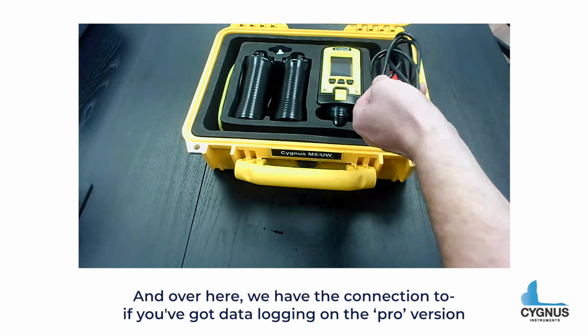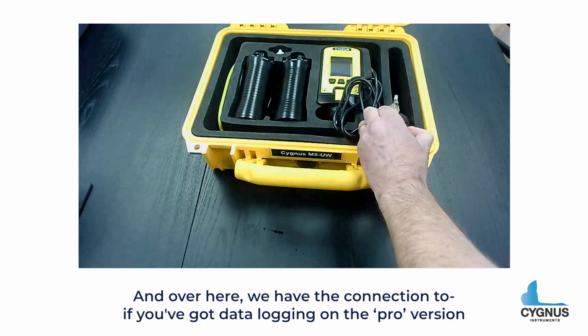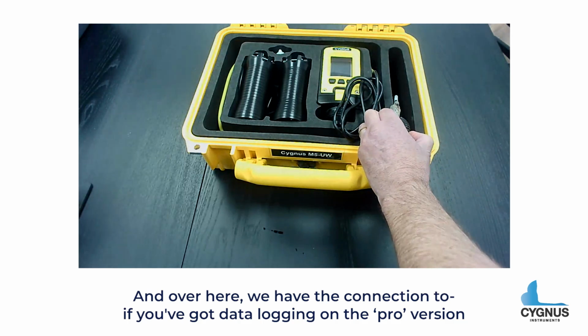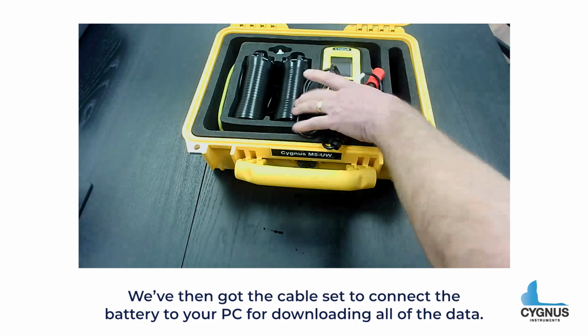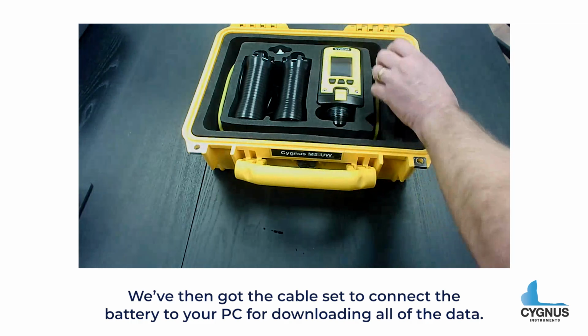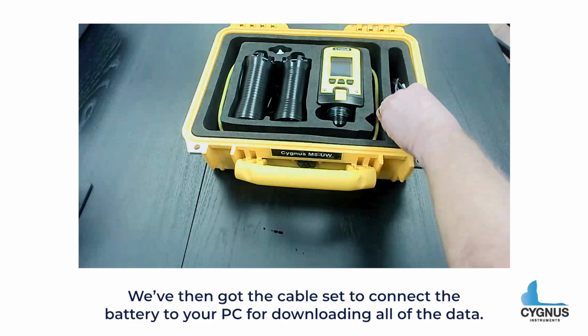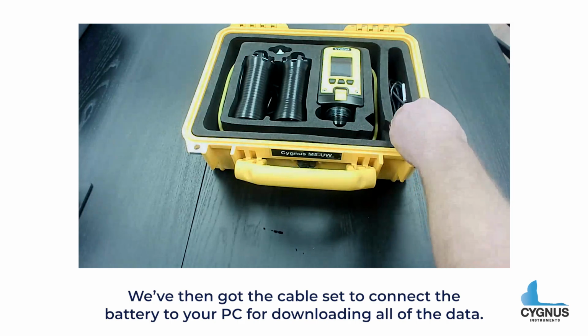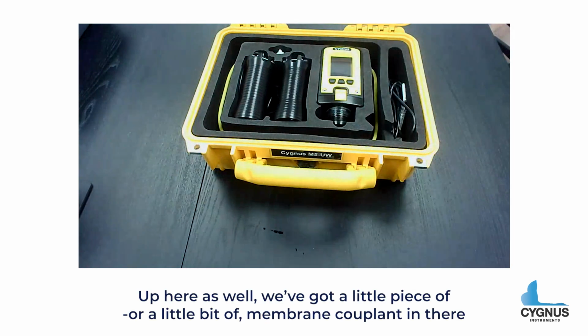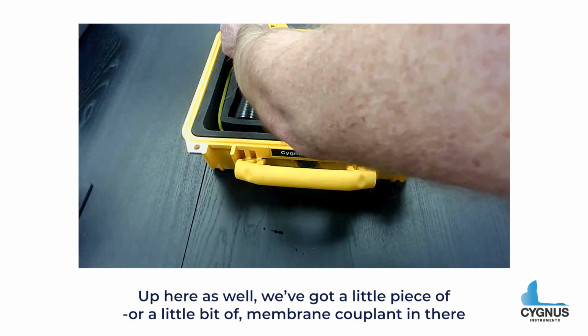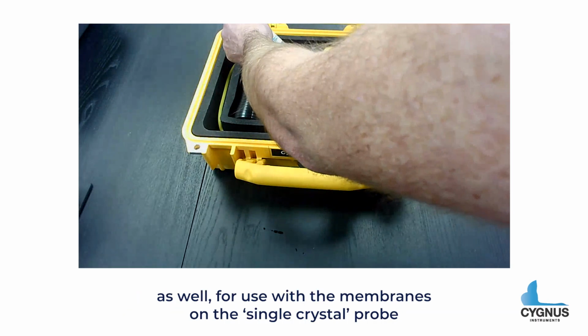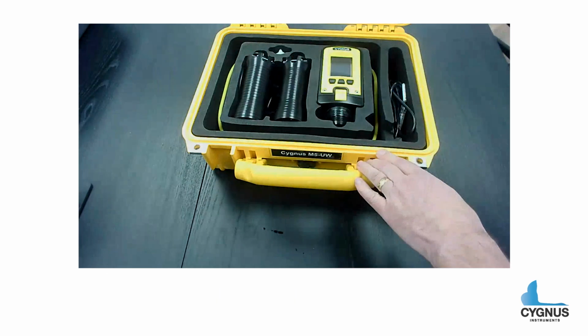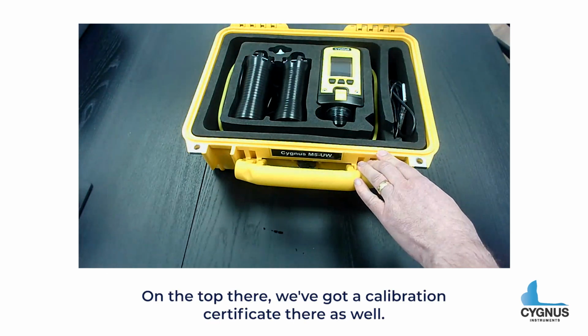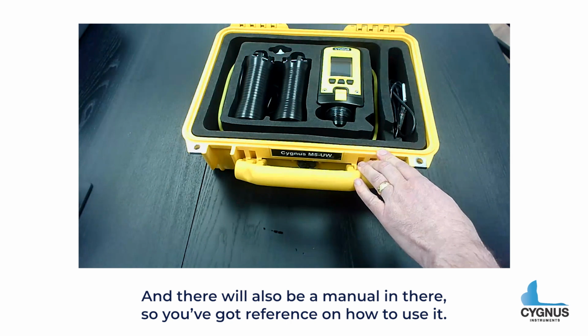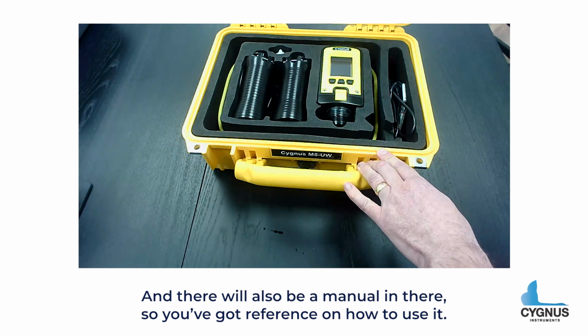And over here we have the connection to, if you've got data logging on the Pro version, we've then got the cable set to connect the battery to your PC for downloading all of the data. Up here as well, we've got a little bit of membrane couplant there as well for use with the membranes on the single crystal probe. On the top there, we've got our calibration certificates there as well, and there will also be a manual in there, so you've got reference on how to use it.